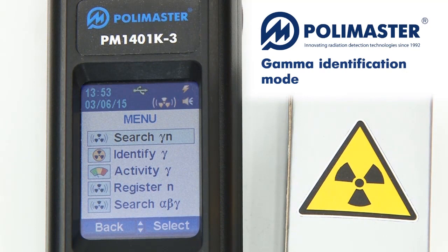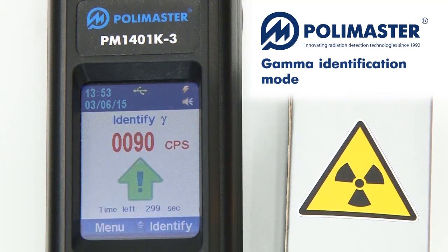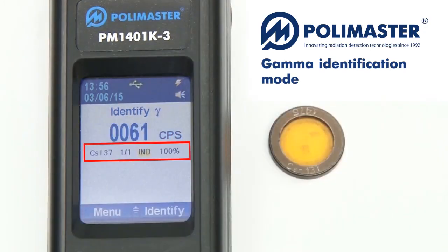PM1401K3 has a built-in function of quick and expert radionuclide identification. For quick identification, choose identify mode in the menu. For accurate identification results, the value of the count rate is to be within the specified range. The optimal value may be reached by moving the instrument closer or farther from the radioactive source. The identification results are displayed on the LCD over time.